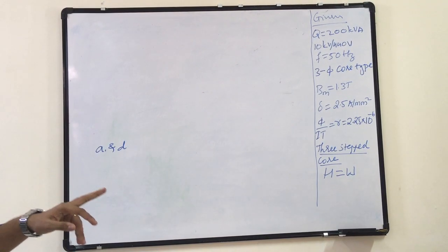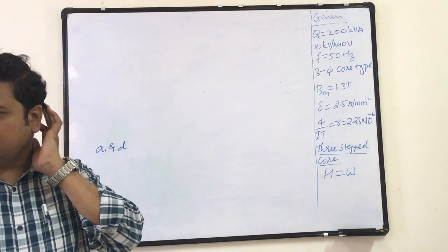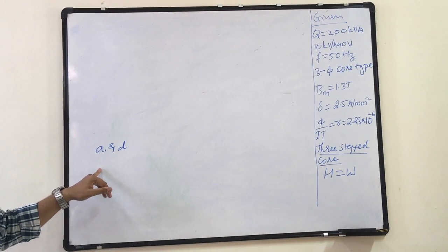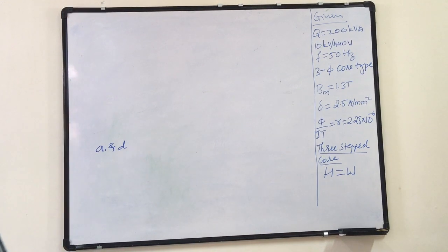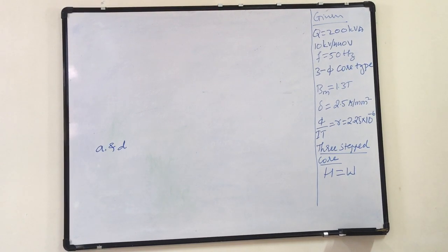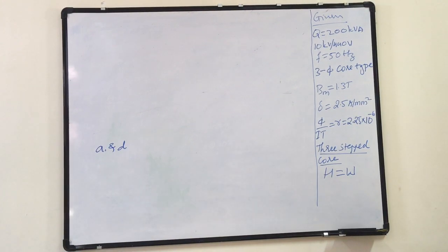A is equal to 0.707 D for single step, 0.85 D for two steps or cruciform, 0.9 D for 3 step and 0.92 D for 4 step. Okay, so that relation I should not forget. So those are the relations for A, and now the relations for Ai.